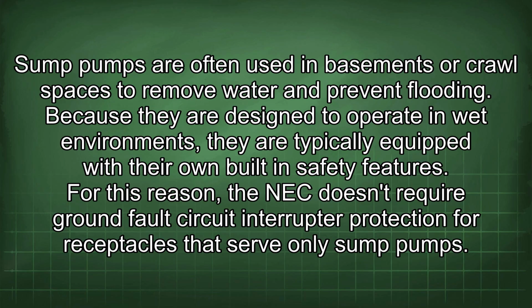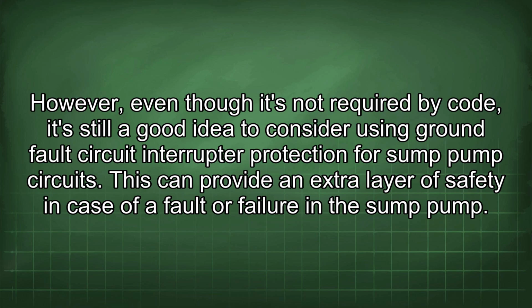Sump pumps are often used in basements or crawl spaces to remove water and prevent flooding. Because they are designed to operate in wet environments, they are typically equipped with their own built-in safety features. For this reason, the NEC doesn't require ground fault circuit interrupter protection for receptacles that serve only sump pumps. However, even though it's not required by code, it's still a good idea to consider using ground fault circuit interrupter protection for sump pump circuits.